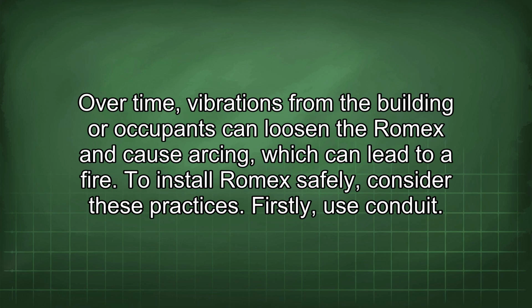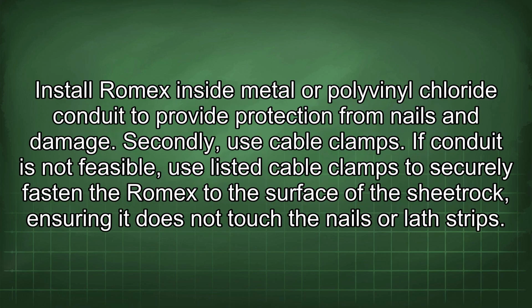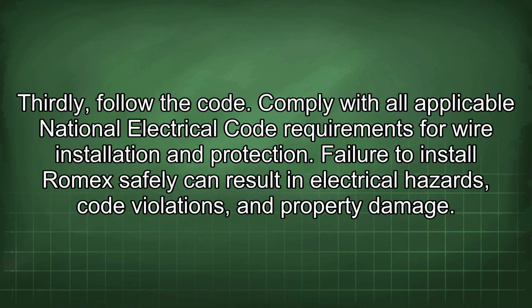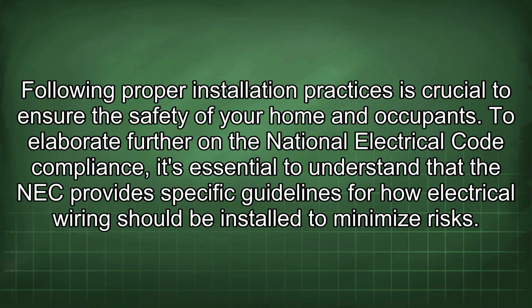Firstly, use conduit. Install Romex inside metal or polyvinyl chloride conduit to provide protection from nails and damage. Secondly, use cable clamps. If conduit is not feasible, use listed cable clamps to securely fasten the Romex to the surface of the sheetrock, ensuring it does not touch the nails or lath strips. Thirdly, follow the code. Comply with all applicable National Electrical Code requirements for wire installation and protection. Failure to install Romex safely can result in electrical hazards, code violations, and property damage. Following proper installation practices is crucial to ensure the safety of your home and occupants.